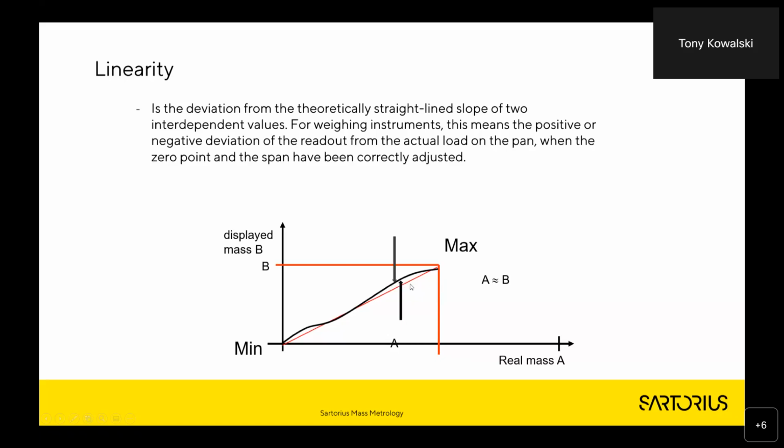So what we look for in a mass comparator, we call this range sensitivity. The difference on the actual slope between the reference and the test weight is almost, if not completely, negligible.